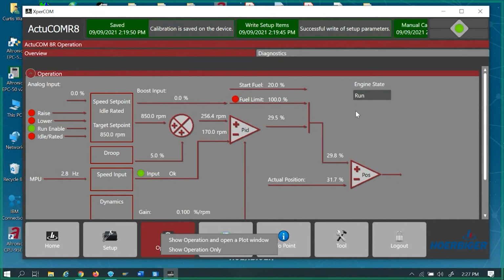If you look at the actuator output, you see I'm supposed to be getting up to 850, and this is where I should be going. My actual position of my actuator is all the way open because I'm falling behind right here. So let me see if I can catch up real quick. Whoa. Now that I've overshot it, you see it's looking for 850. Now my actuator's shutting off because I'm over it.